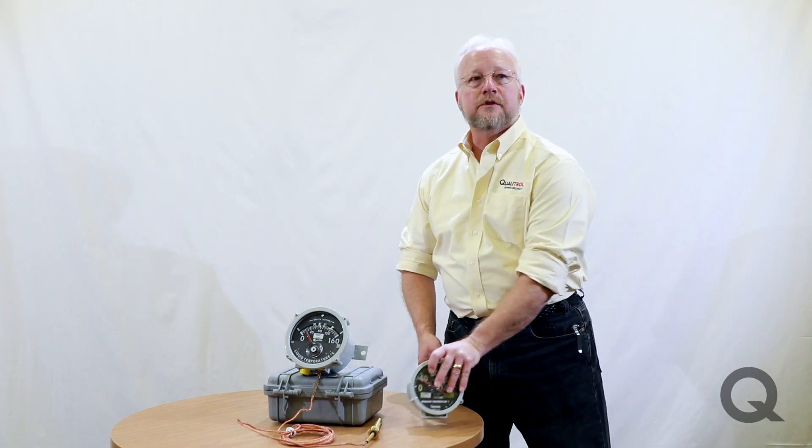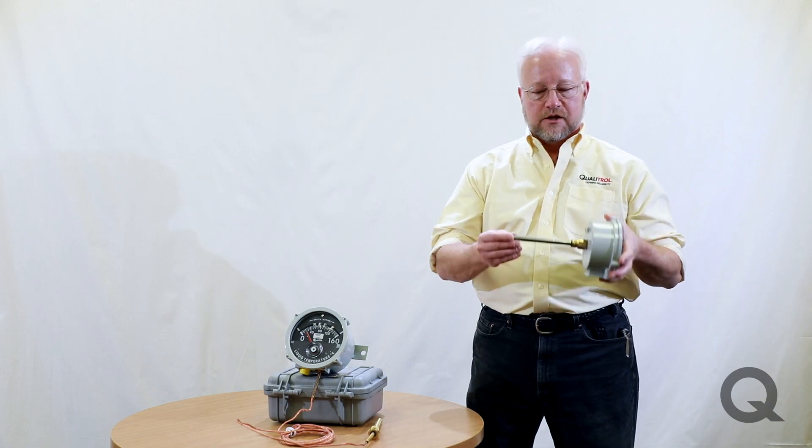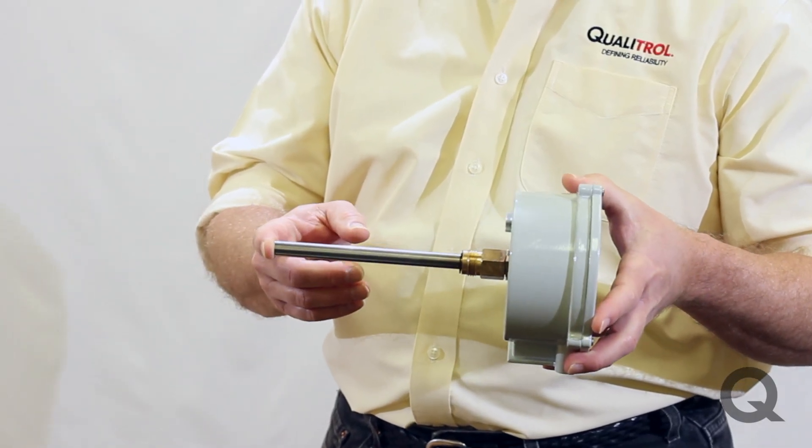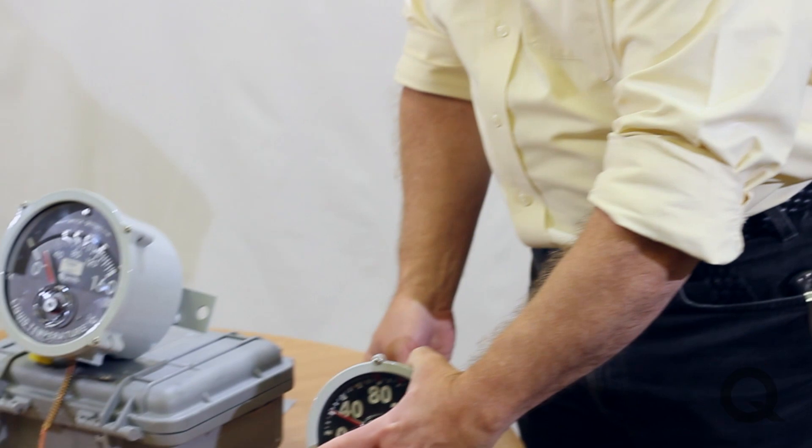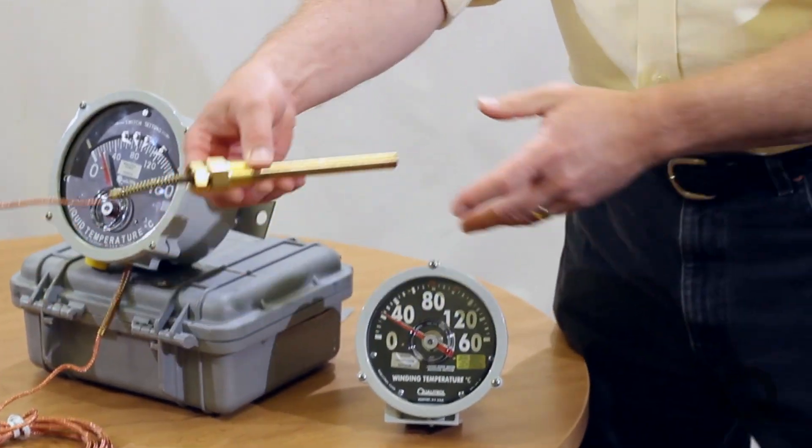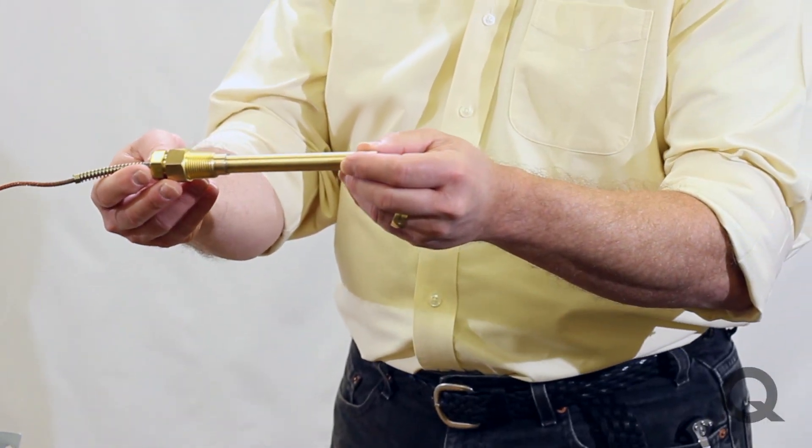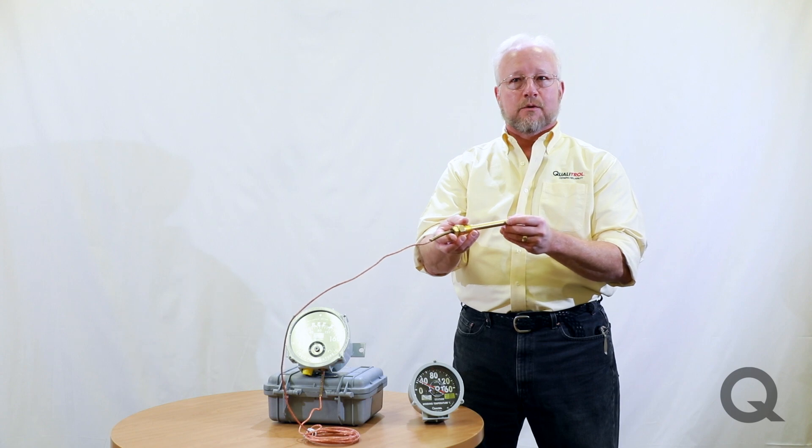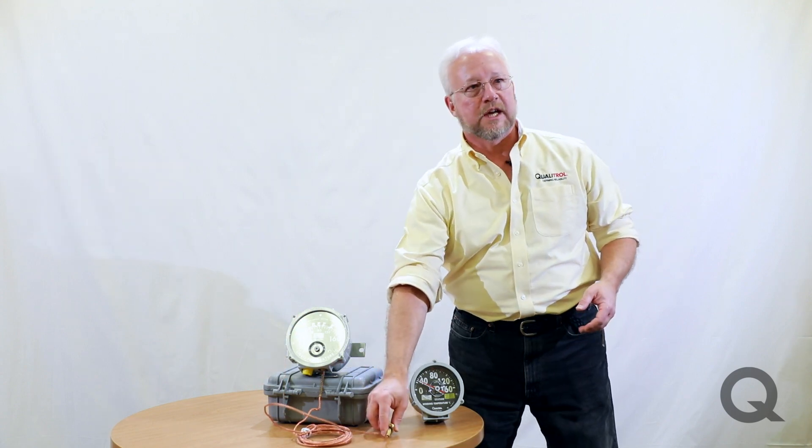There are two basic types of thermometers, one's the direct mount and the other one is the remote mount. The direct mount is fairly easy to tell because it's got a probe coming straight out the back. The remote mount will have a capillary tube that's connected to the probe that goes right into the transformer dry well at some remote location.